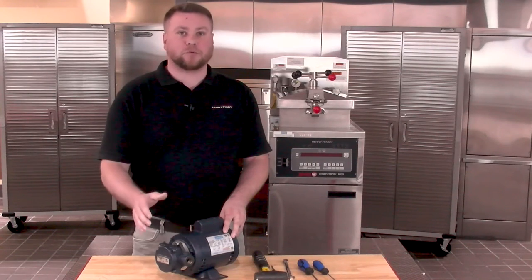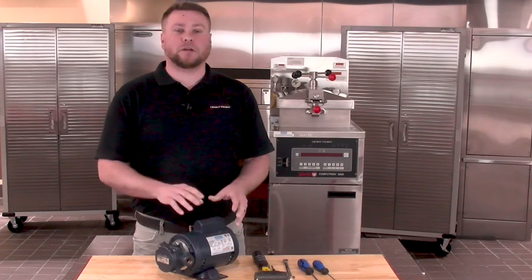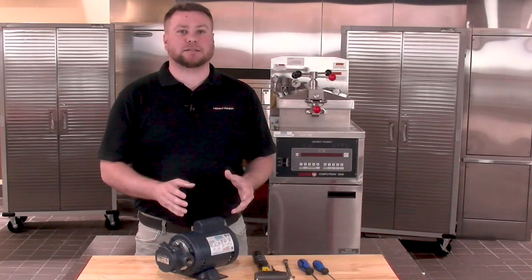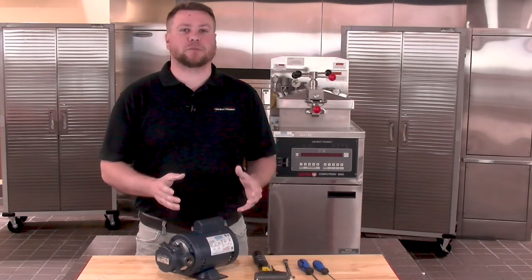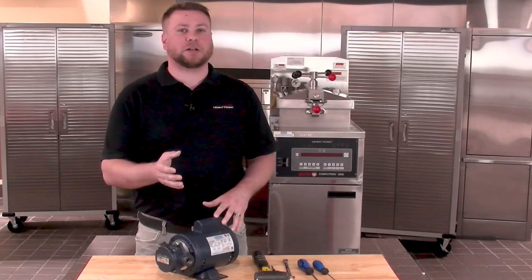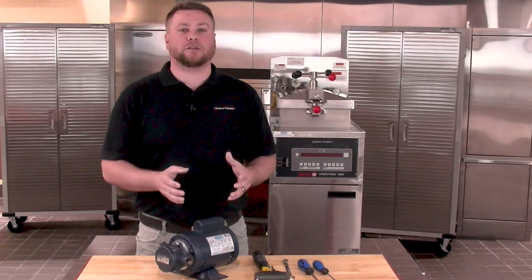Keep in mind, any time that we're rebuilding the pump, or we find a leaking seal, or in the event that we're replacing a motor, the seal kit should be replaced at this time. This job is performed easiest at a workbench, just like the one we have in front of me, but depending on which model you are working on, this can also be performed while on the fryer as well.